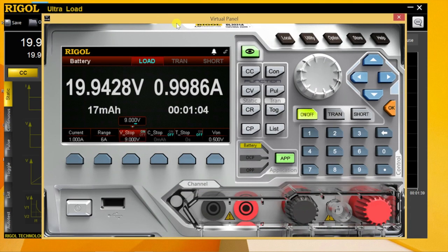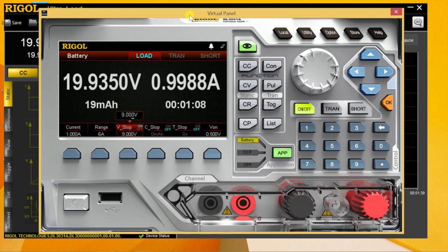Lastly, if we are working remotely, we can always open the virtual front panel. And then we can see exactly what we want on the front panel at any time. This is another great way to work with your load when it's in a test bay or a position that's hard to get to physically or where you need to work remotely to analyze your data.